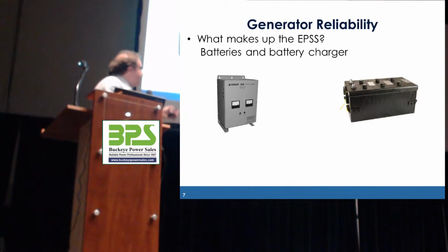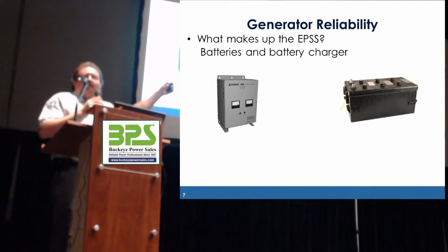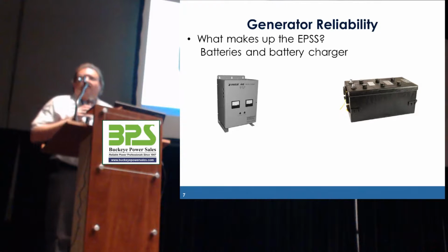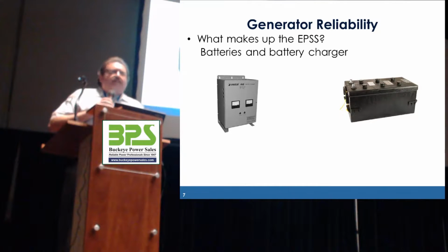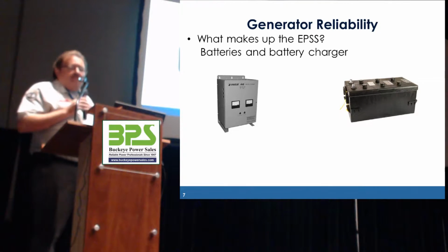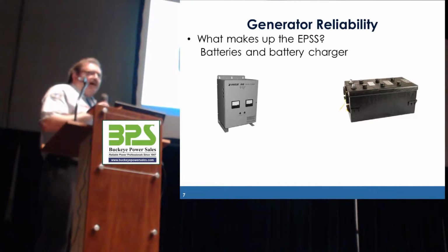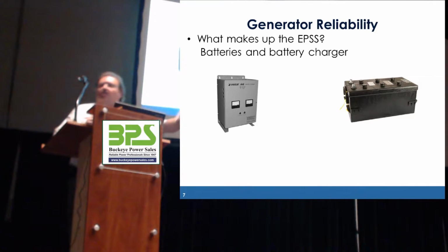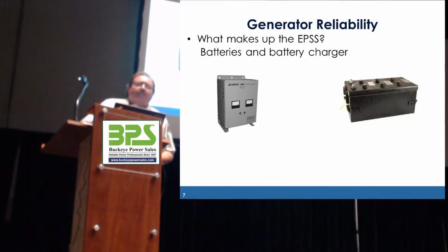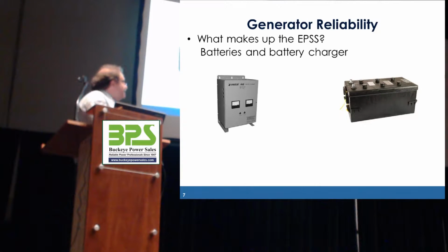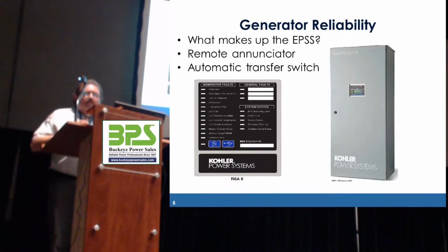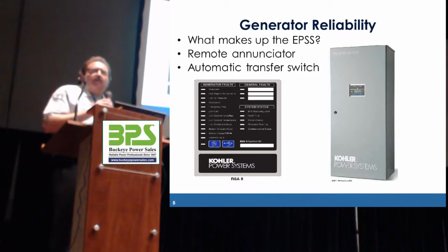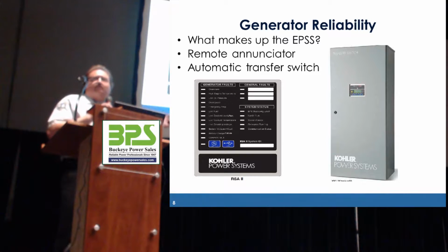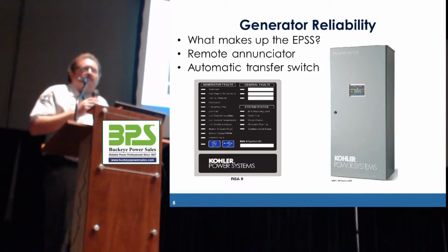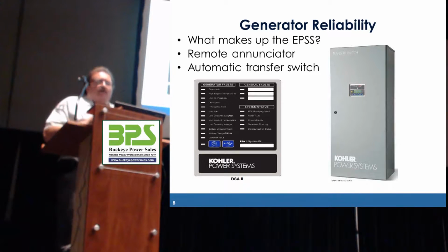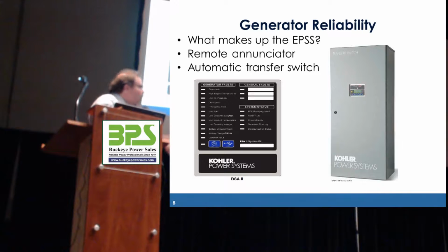We talk about the batteries and the chargers. The batteries on that generator are probably the weakest link on the generator, right? That battery fails, that generator's not going to start. We have battery chargers because the controls are always draining power from those batteries, so we have to have a charger to keep them charged up. You have to have a transfer switch or some sort of a device that switches between the utility source and the generator. We also have remote annunciators.